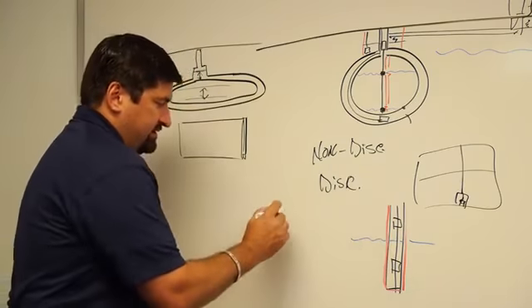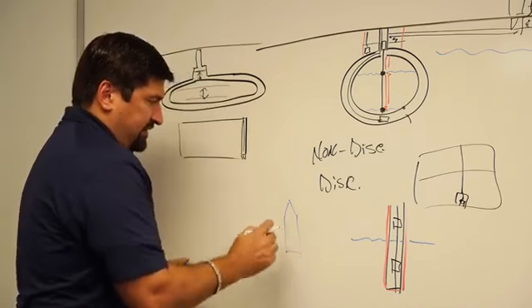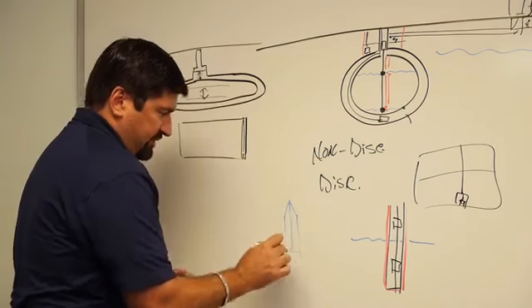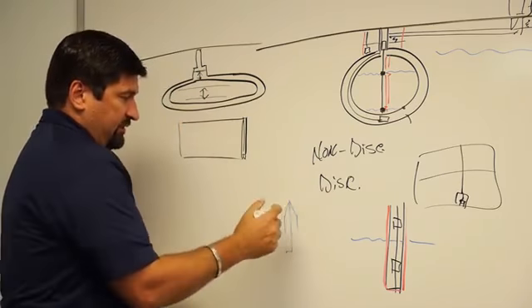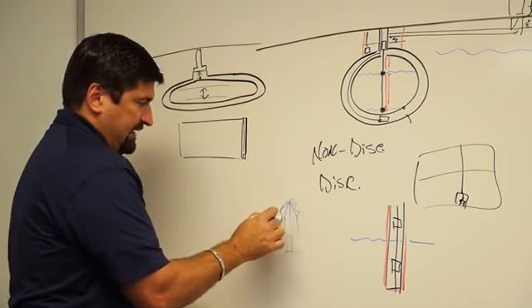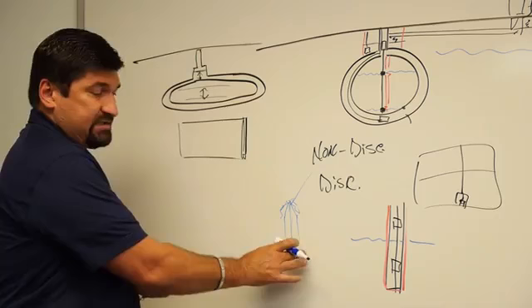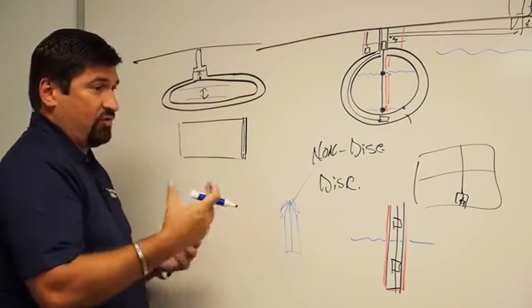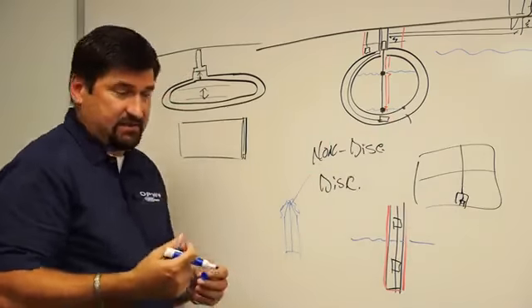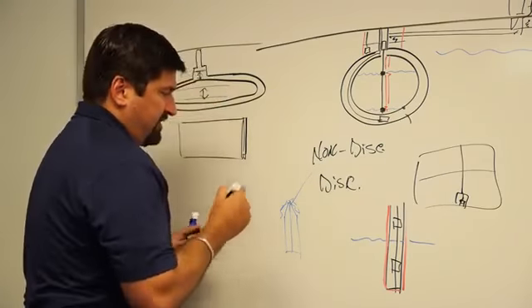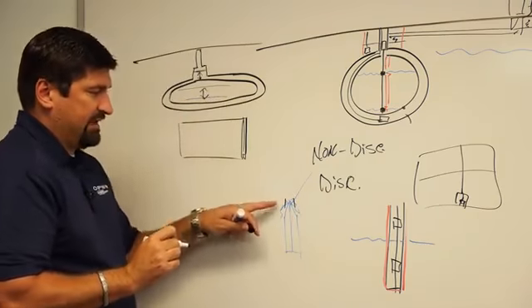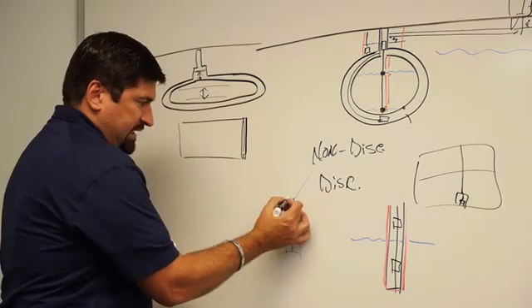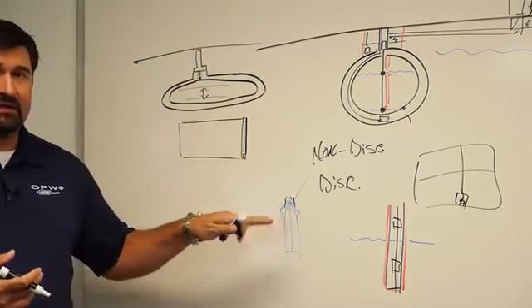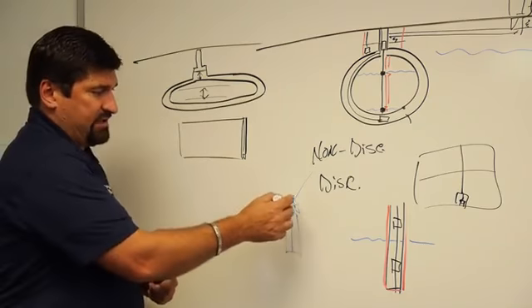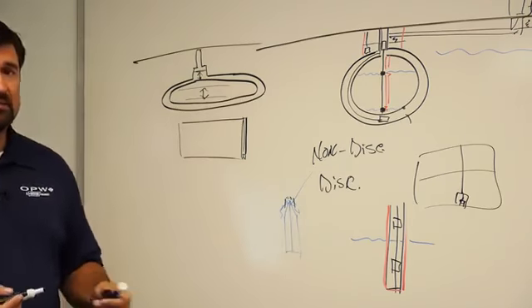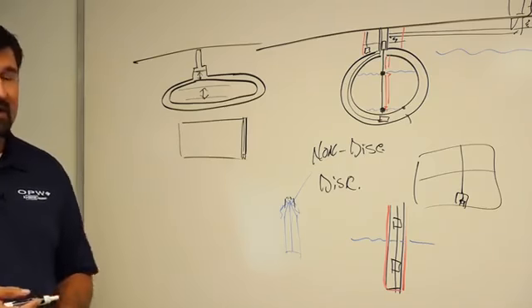The other way that they do it is through an optical sensor. An optical sensor just sends a beam of light to a prism, and if the light is reflected back, it knows that there's no liquid on the outside of the prism. Well, once you put liquid on the outside, this light is just reflected away and it's not returning back to the source. This is just a normal, non-discriminating sensor. By the addition of continuity pins in the interior or the exterior of this prism, what it's doing is reading continuity between these two pins, water being conductive and fuel not being conductive. It knows that there's a liquid present, and it looks at the continuity between the pins. If I've got continuity, it's water. If I don't have continuity, it's fuel.